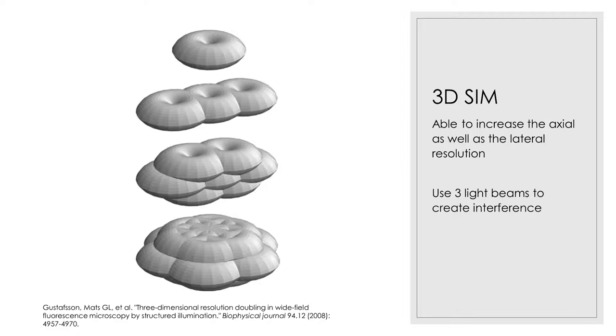In 2D-SIM, the sample was illuminated by two beams of interfering light. In 3D-SIM, three beams of light are used to produce a 3D excitation pattern. And this contains more Fourier components, so more image information can be obtained, which can fill in the missing cone and double the Z resolution.